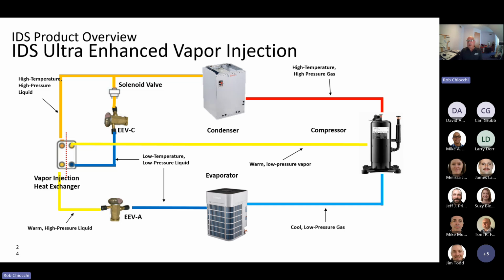can absorb, allowing this to operate and absorb heat from very cold outdoor air at parameters well below what a standard heat pump can do. It's not a complicated system, not a whole lot to go wrong there. And I think Bosch has done a really phenomenal job with incorporating the system into their Ultra heat pump.